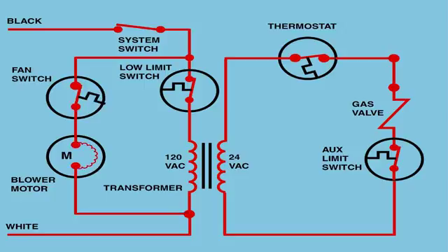When it reaches the low limit switch setting, the low limit switch opens and cuts off power to the transformer. If the thermal protection on the blower motor has opened or the blower motor has just failed, then if you listen carefully, you'll hear the burner cycling on and off on the low limit switch, and the blower never comes on.